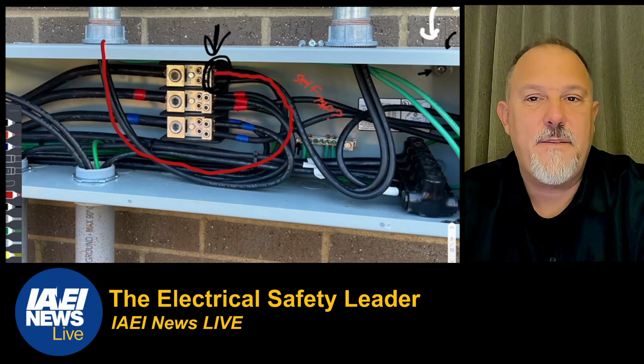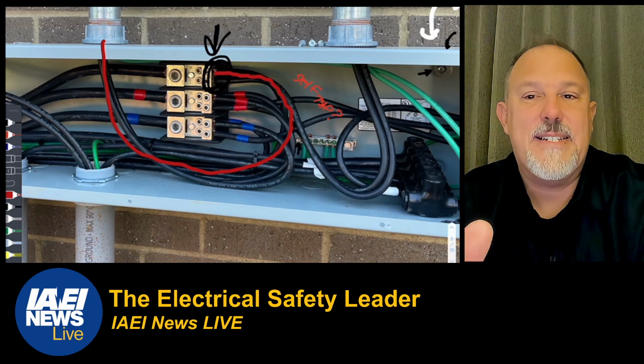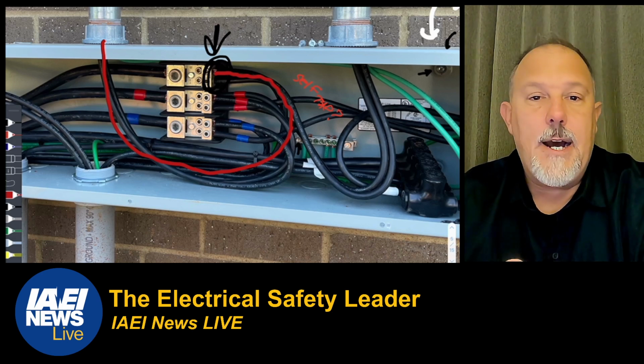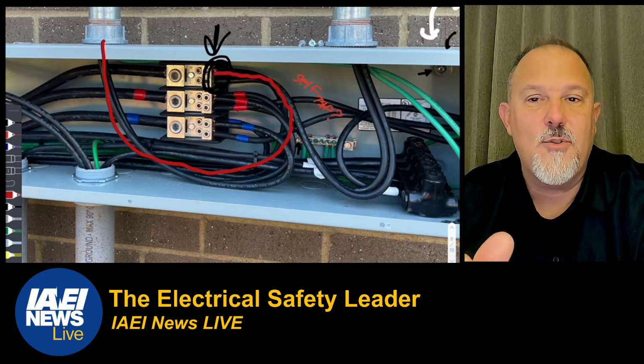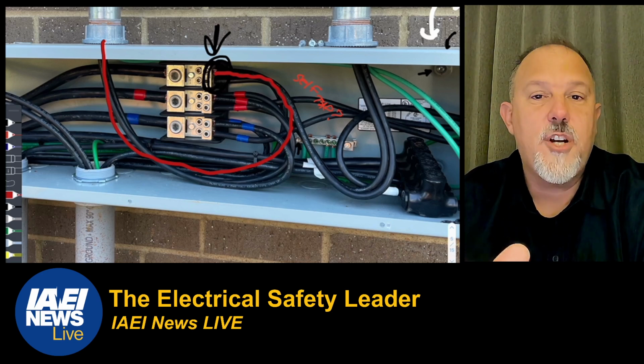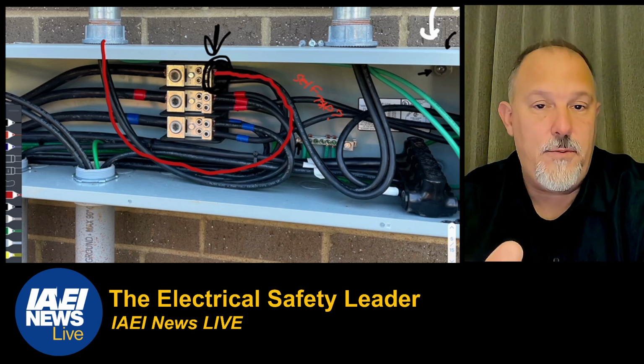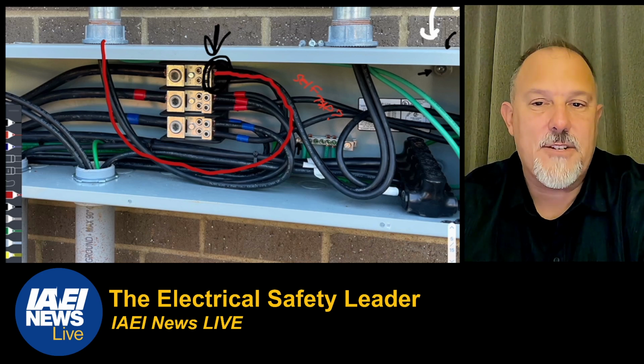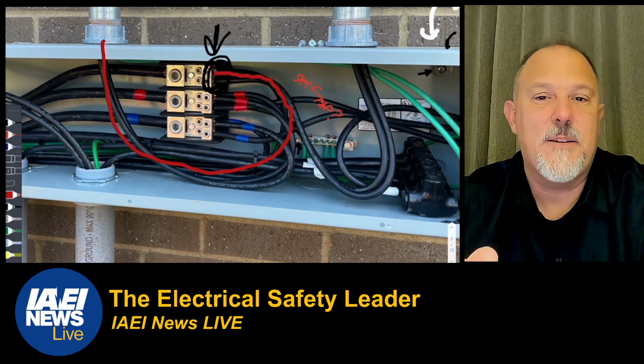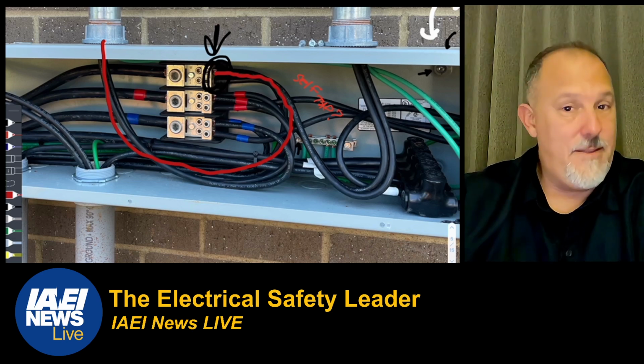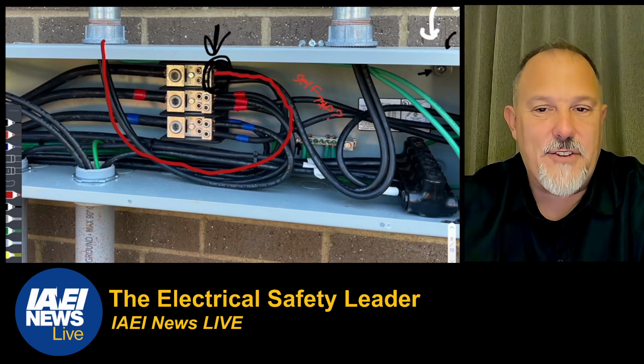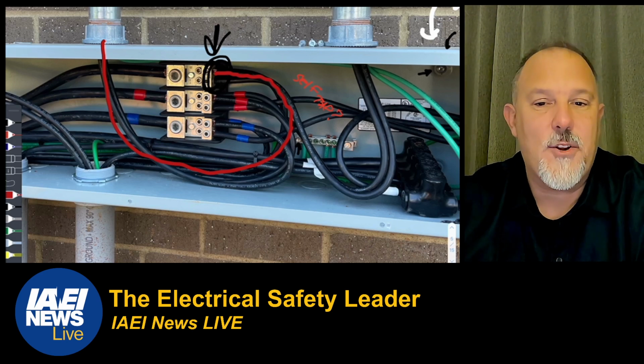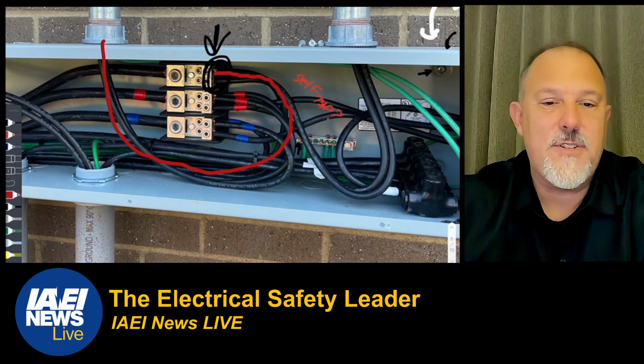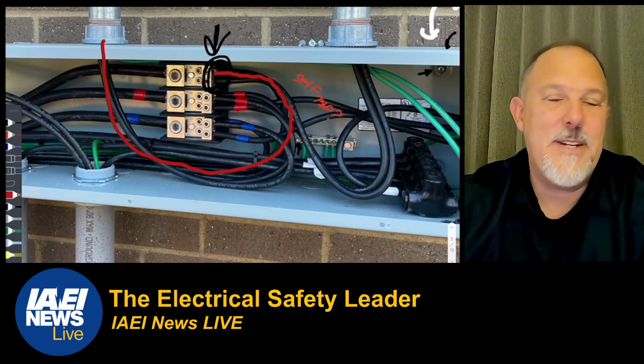The tap conductors are protected from physical damage. These are. The tap conductors terminate at a single circuit breaker or in a single set of fuses. These do. The overcurrent device for the tap conductors is an integral part of a disconnecting means or shall be located immediately adjacent thereto. The disconnecting means for the tap conductors is installed at a readily accessible location complying with one of the following: outside of a building, these do; inside nearest the point of entrance of the tap conductors; or where installed in accordance with 230.6, nearest the point of entrance of the tap conductors. So outside taps, can they be unlimited length?